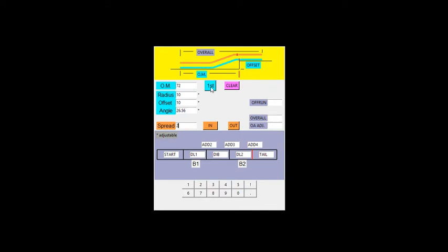So let's go ahead and I've input my parameters for this bend. This OM is your obstruction measurement from the end of your last conduit to your obstruction. The offset is just the height of your obstruction. The radius is center line of your bending shoe radius, and your angle is whatever angle you choose, but I picked 26.56 because it's a 2-to-1 ratio on your offset triangle. Okay, and then all I got to do is four simple inputs. That's it. Boom, there's all your numbers right there.